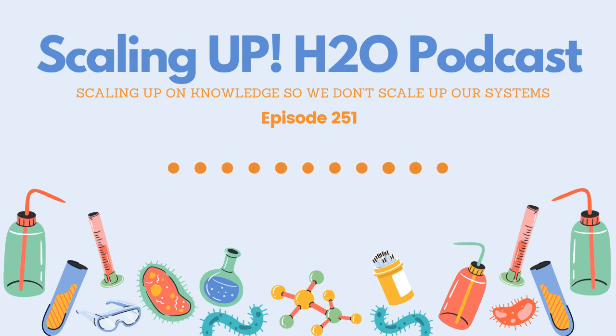And now you've got a calibrated and clean probe. You put that back in the system and it should measure exactly what your meter is reading. Well, I say exactly, it should be pretty darn close. And if it is, now you need to determine if that's in range or if it's not. If it is low, then did calibration fix it? Well, maybe it thought it was falsely high and it was calling for bleed when it didn't need to do that. Well, you just fix that with the calibration. Or maybe you didn't. Maybe there's some other issue going on.